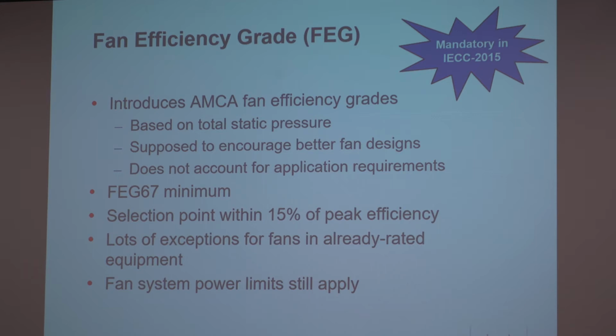But in addition to the FEG, or fan efficiency grade, we have this thing called the system fan power limit. And the system fan power limit is in horsepower per CFM, and the horsepower per CFM is for the whole system. So if you've got a fan system with 300 feet of ductwork, it's going to have maybe a little bit harder time meeting it versus a fan system that only has 75 feet of ductwork on the critical run. So designing systems well is certainly something the system fan power limit is going to constrain you on and require you to do.